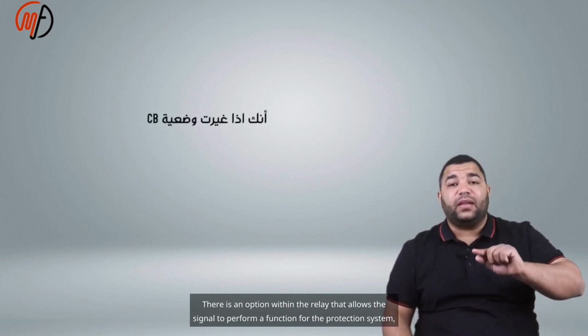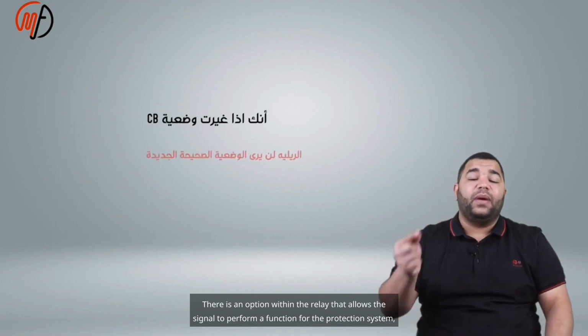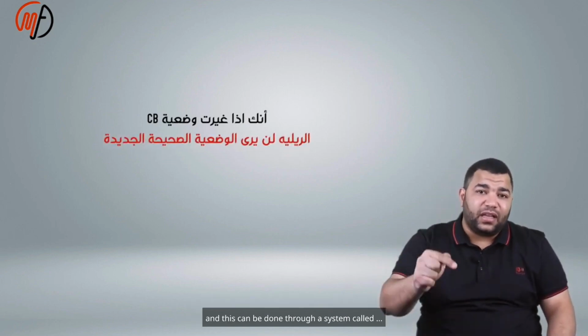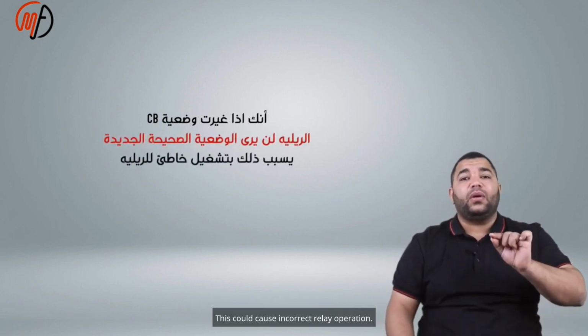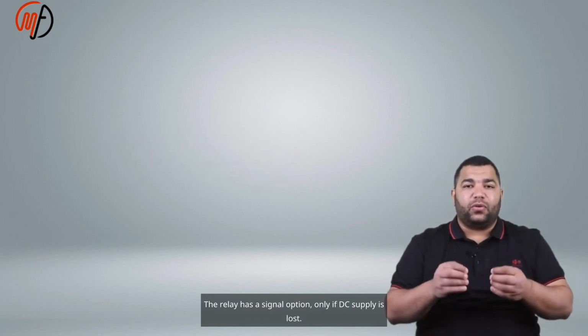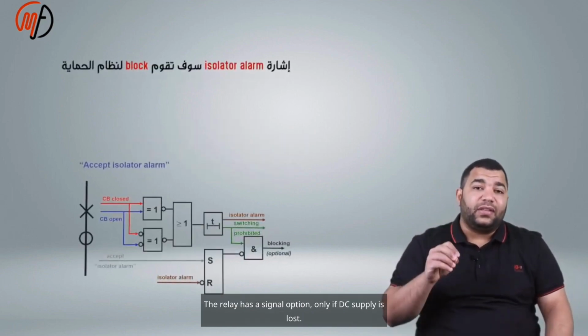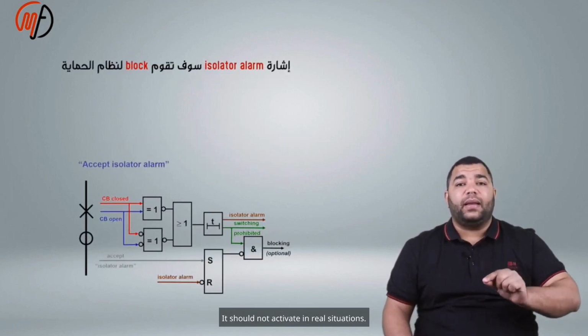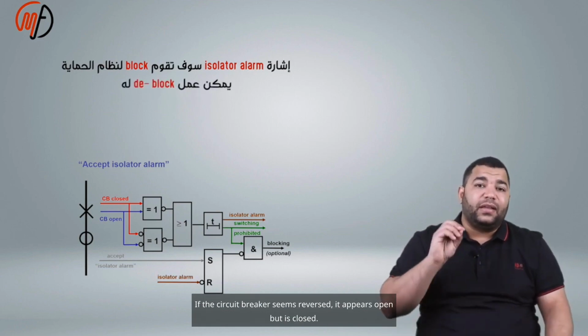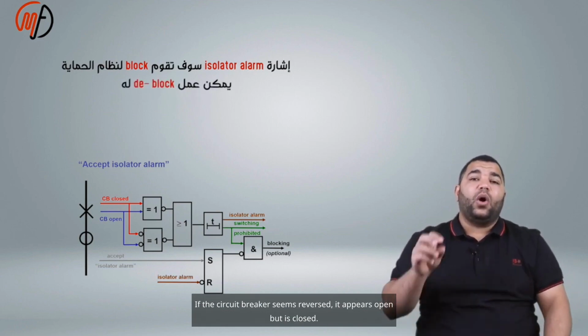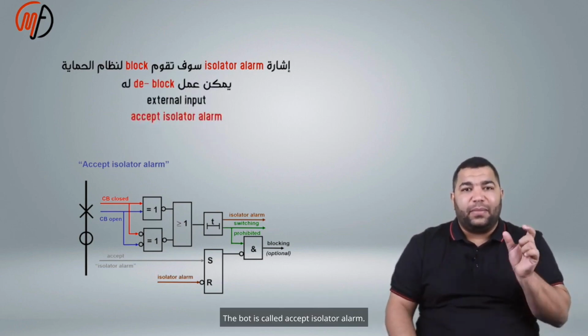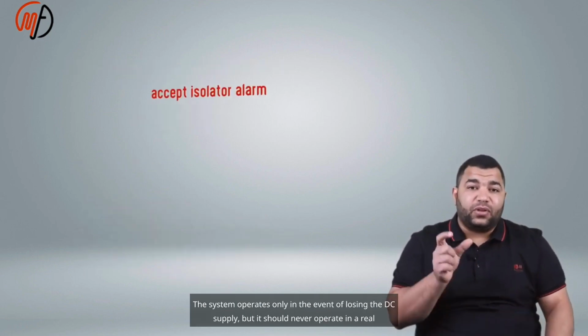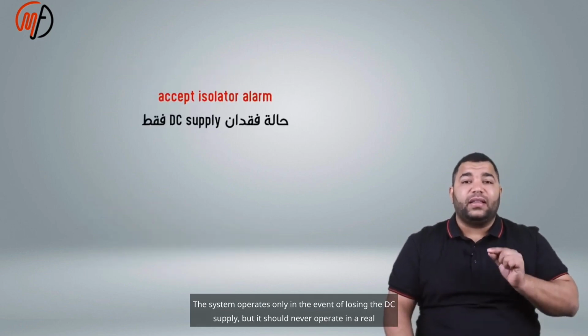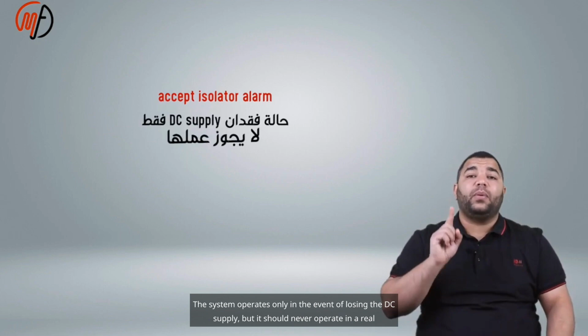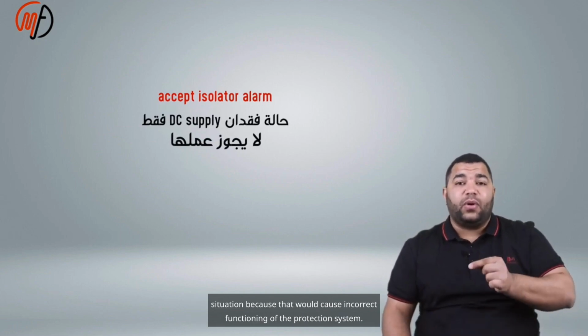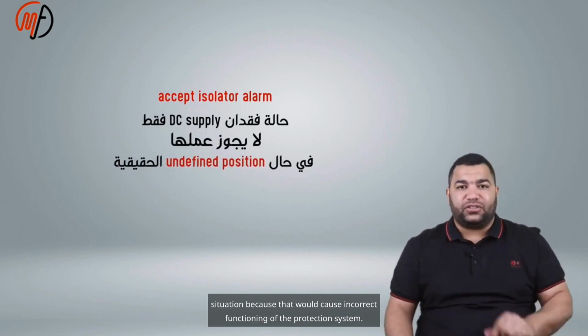There is an option within the relay that allows the signal to perform a function for the protection system, and this can be done through a system called Accept Isolator Alarm. The system operates only in the event of losing the DC supply, but it should never operate in a real situation because that would cause incorrect functioning of the protection system.